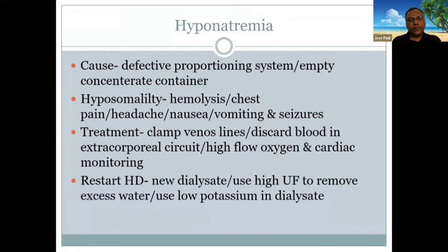Hyponatremia again is due to a defective proportioning system or an empty concentrate container. It can lead to hypoosmolality characterized by hemolysis, chest pain, headache, nausea, vomiting, and seizures. Treatment is to clamp the venous line and discard the blood in the circuit. You should use high flow oxygen and cardiac monitoring, and restart dialysis using a new dialysate. Use a high ultrafiltration rate to remove the excess water. And you have to use low potassium in the dialysate, because high potassium also can contribute to this condition.